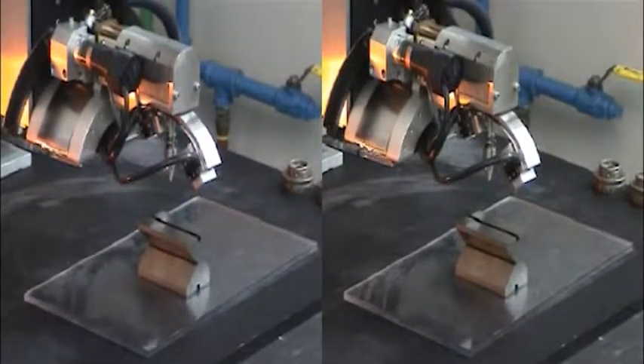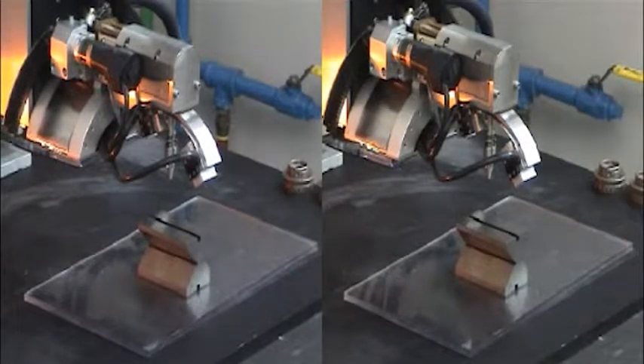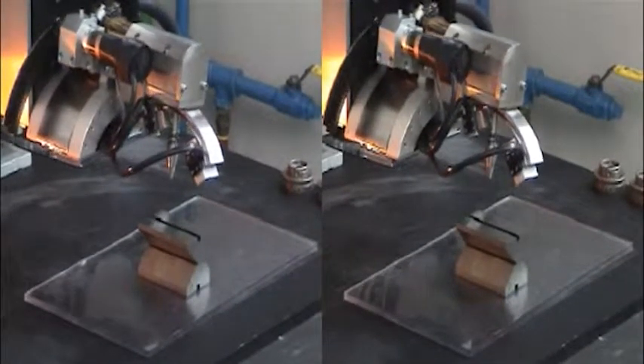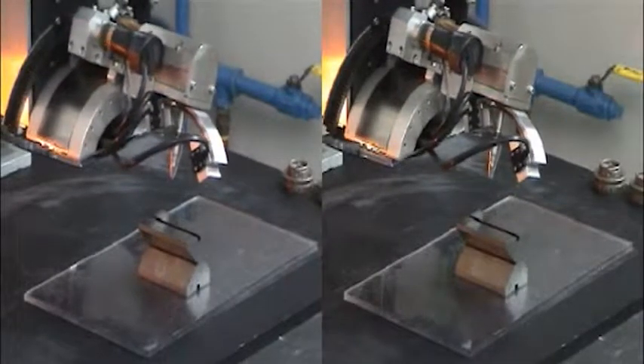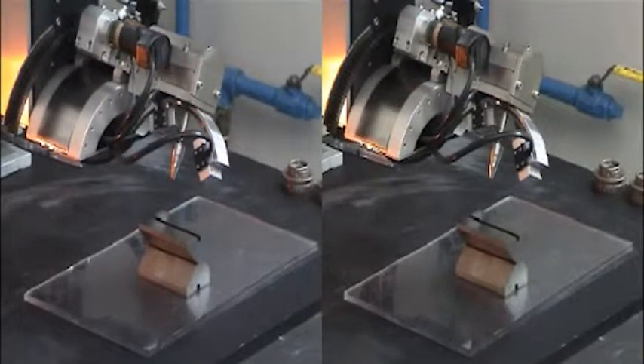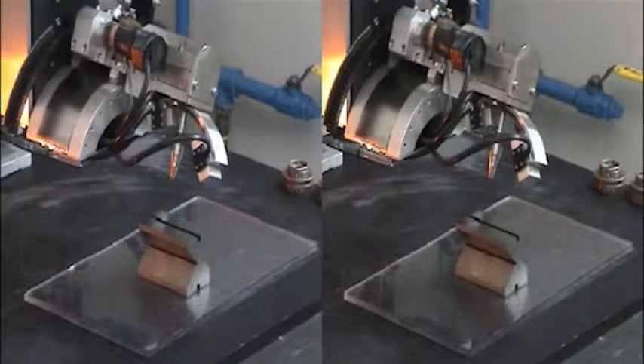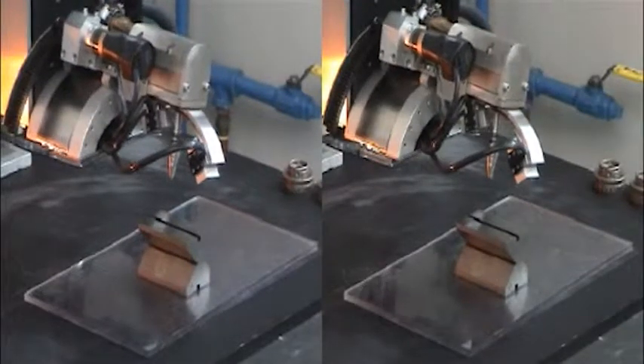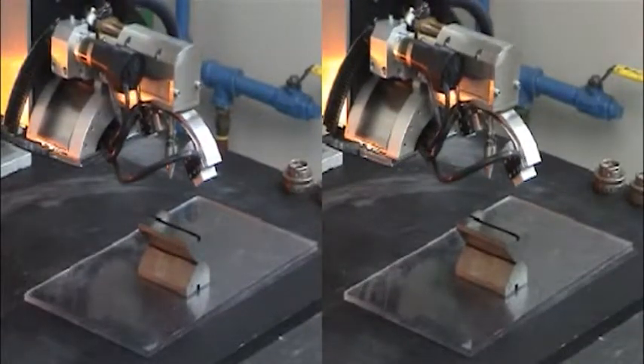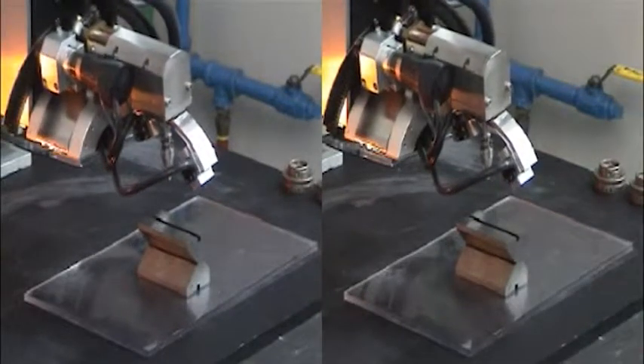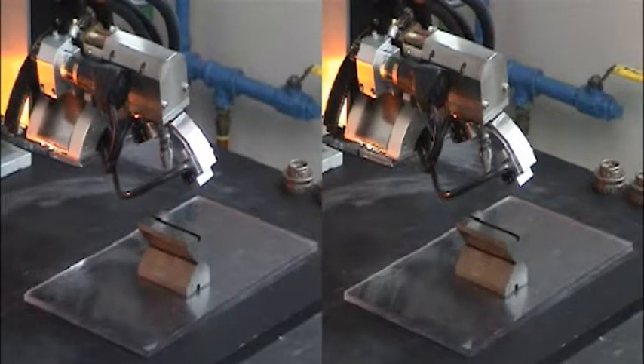The head emits X-rays, and there's a little detector on the side that detects the diffraction of those X-rays, which is measured as a function of the angle with respect to the part. All this information is gathered, and the end result is to essentially calculate the spacing between the atoms, which is related to the residual stress.